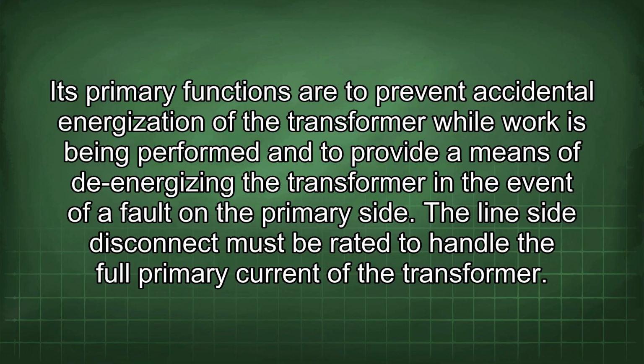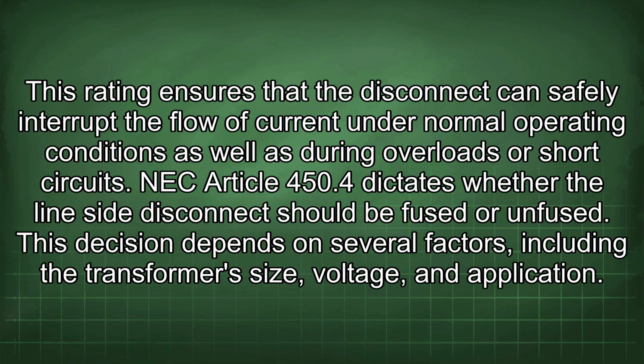The line side disconnect must be rated to handle the full primary current of the transformer. This rating ensures that the disconnect can safely interrupt the flow of current under normal operating conditions as well as during overloads or short circuits. NEC Article 450.4 dictates whether the line side disconnect should be fused or unfused. This decision depends on several factors, including the transformer size, voltage, and application.